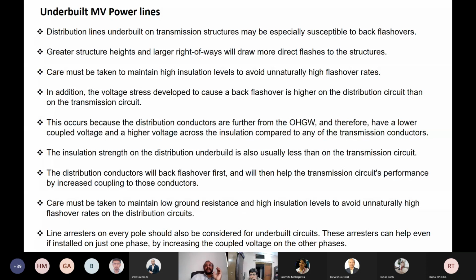So greater structure heights and larger right of ways will draw more direct flashes to the structures. Then care must be taken to maintain high insulation levels to avoid unnaturally high flashover rates. So you have to be very careful in this regard, because people tend to go for underbuilt medium voltage lines because it's much less costly to maintain such systems, as you do not need a special power line corridor. You can use the same power line corridor used for the HV line.